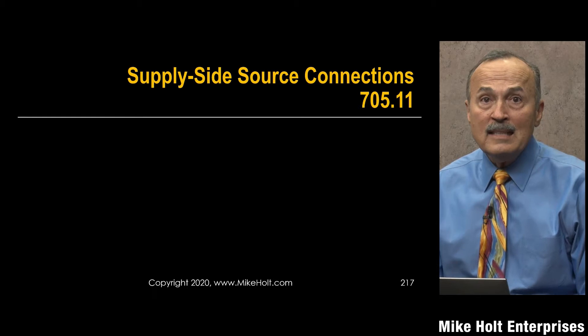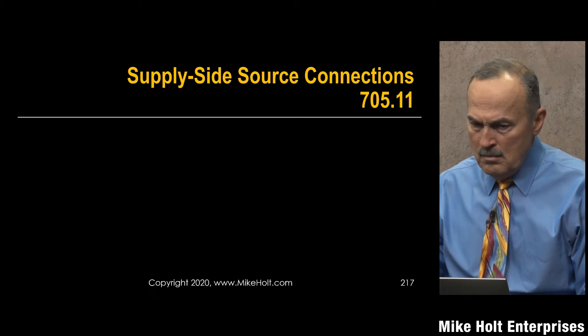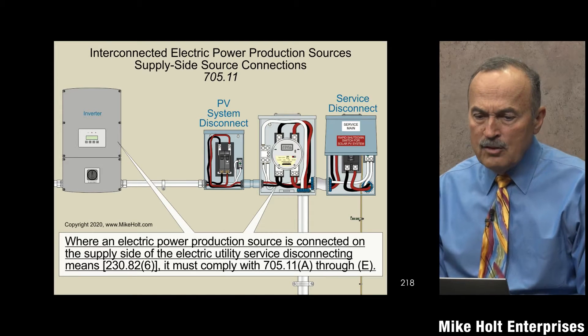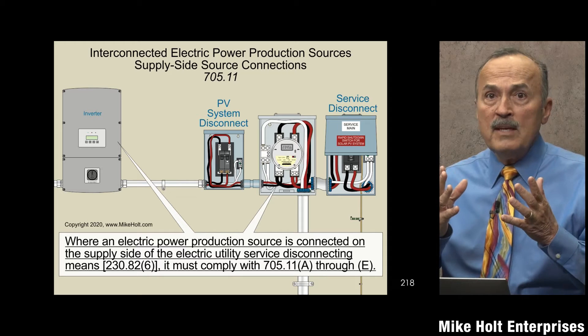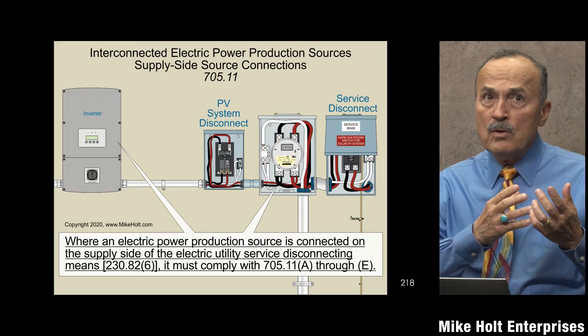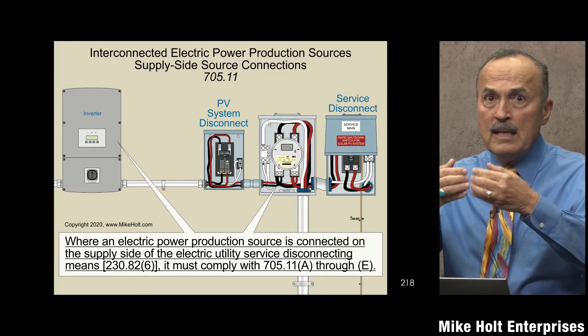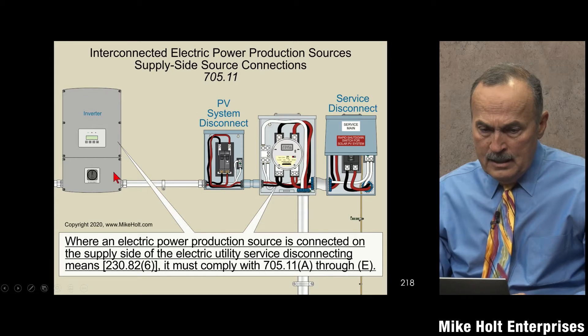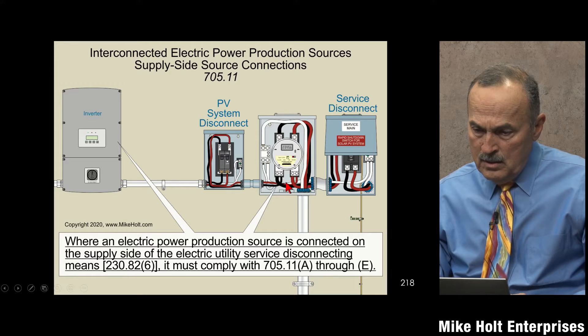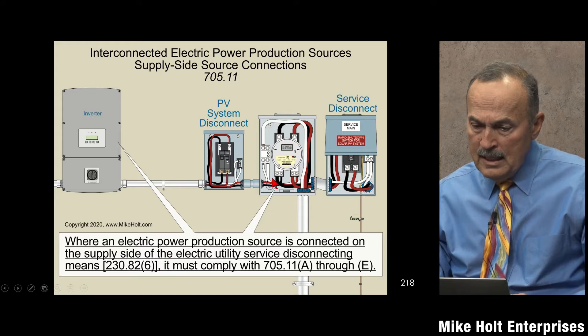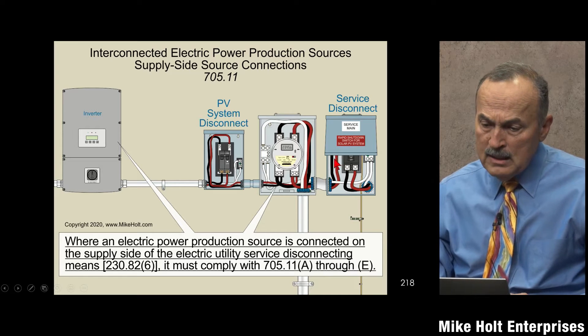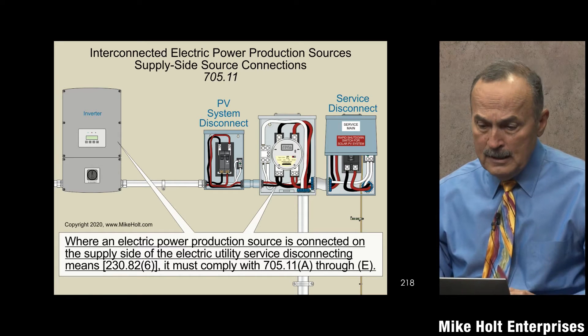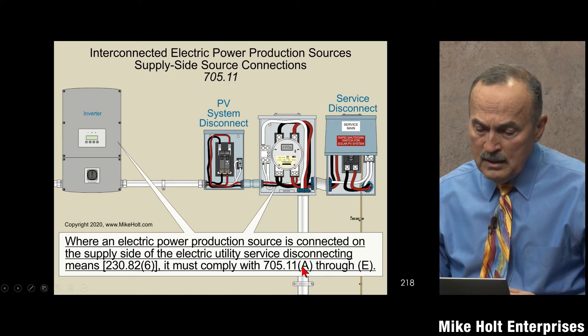Supply side source connections — NEC 705.11. Using a PV system as an example, the output conductors of the inverter connect to the utility, making the interconnection on the supply side. Here's your service disconnecting means — this connection is before that disconnect, not after. So when an electric power production source is connected on the supply side of the utility service disconnecting means, we have to comply with 705.11, items A through E.